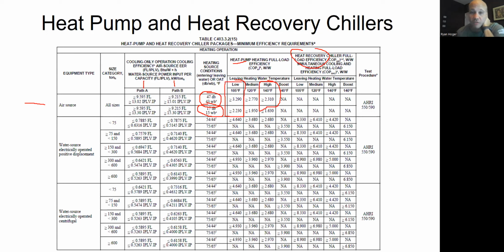And then if you have a heat recovery chiller, which means you don't have a reversing valve inside the chiller, you're going to reverse things on the water side, or you're going to be running simultaneous hot water and chilled water, which is mostly what you're going to do. Then you'll be in this other column, and it works the same way. There's nothing in there for the air source side because you won't have this on the air source side. You'll be doing this only with water-to-water chillers, because the condenser water loop and the evaporator water loop have to switch jobs. So they both need to be doing water.